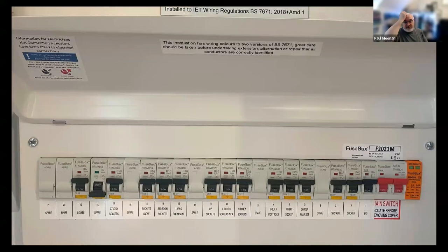Now, this is my favorite picture of all time. It's my fuse board downstairs, and that is what I call a minimal viable product. It is a fuse box, a very witty pun from the manufacturer. It's actually a consumer unit. What I have there is my installation. It's a 21-way board, and I've labeled it all up. Each one of those devices, except for the surge, is an RCBO.